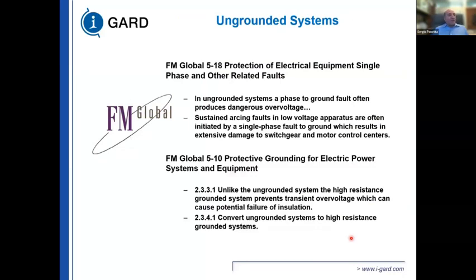Even FM Global, the insurance company, used to give out discounts to people who moved from an ungrounded system to a different type of system, because they realized that with ungrounded systems you inherently get more damage because ground faults are prevalent. And when they are prevalent, you tend to have more ground faults and more damage due to the ground fault. And the inability to locate the ground fault means that they're on the system for longer periods of time. So in ungrounded systems, a phase to ground fault often produces dangerous overvoltage, which we just saw from Beeman's book. Sustained arcing faults in low voltage apparatus are often initiated by a single phase to ground fault. So obviously all faults begin as single phase to ground faults.